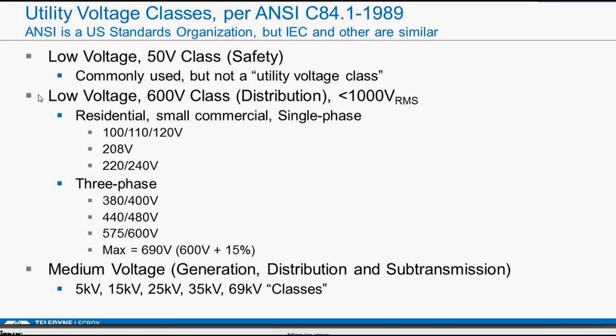Then the utility voltage classes are low voltage, which for those used to working with printed circuit boards where 20 volts might be high, 600 volts in this case is low voltage. And that's what's called the distribution class. This is basically less than 1,000 volts RMS. It's called the 600 voltage class. It encompasses 400 volts in Europe, 600 volts in Canada, 480 volts in the U.S., and everything kind of in between. And it encompasses all the residential and small commercial single-phase voltages and these higher voltages as well.